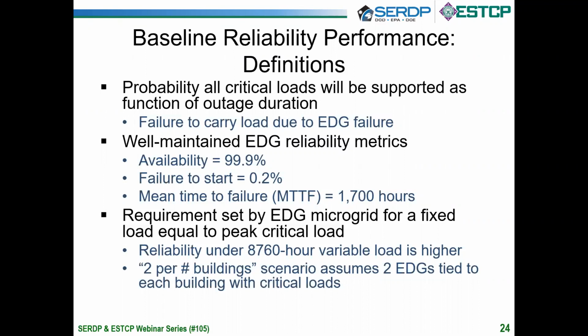So in the baseline diesel generator system, the only reason you have failure, assuming as we have that we have sufficient fuel available on the base, is if a diesel generator fails or is unavailable during the outage. And the outage could take place at any hour during the year. And so you have to assume that the outage may start from January 1st, right after midnight, or at December 31st, and it can run up to a week.